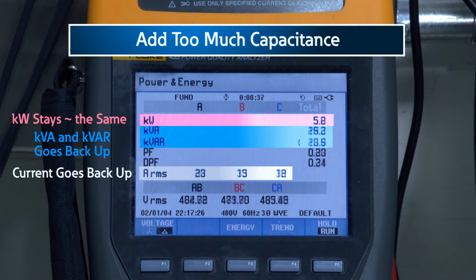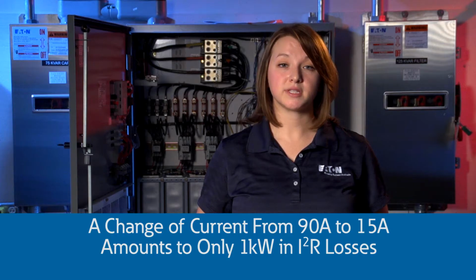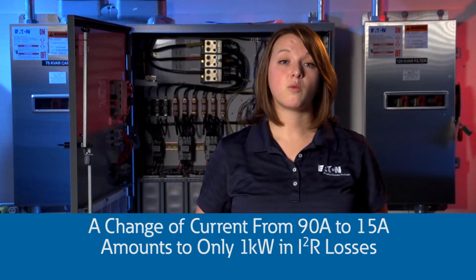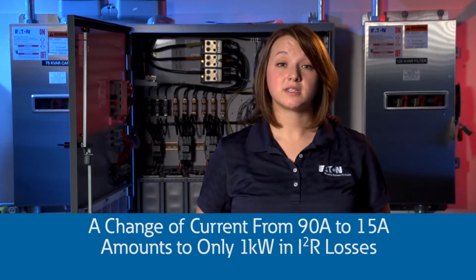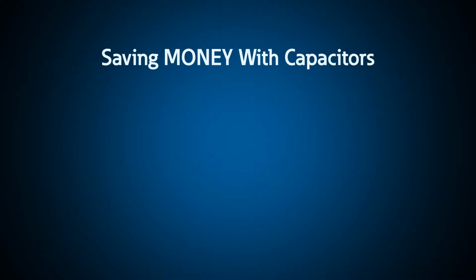Still, even with a larger change in current from about 90 amps down to 15 amps, we aren't saving 80% of the kW. There's less than a 1 kW difference related to the I²R losses. Since our bill is based on our kilowatt hours in our home and primarily based on the kilowatt hours and the kW demand for our business, we are not saving real power or money off of your bill. However, saving money and saving energy are not the same thing. Even though they do not save significant power or energy, capacitors can save money in the following ways.